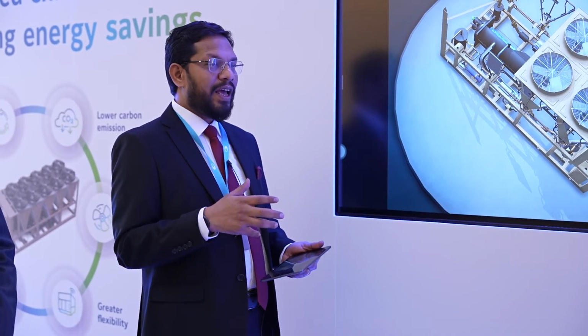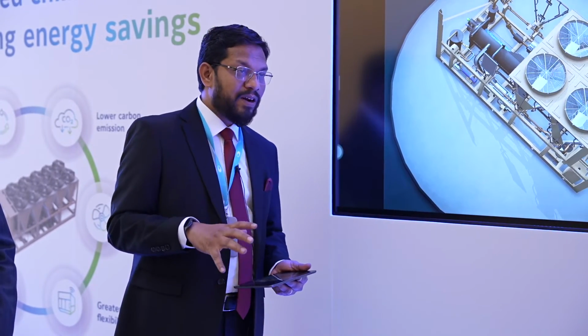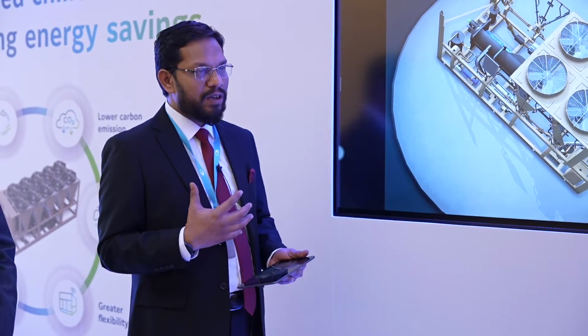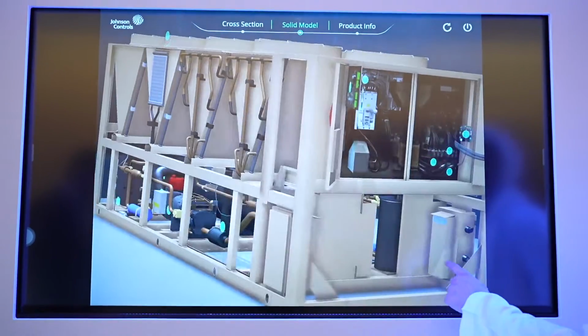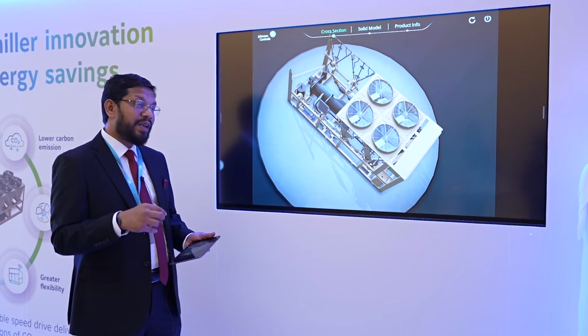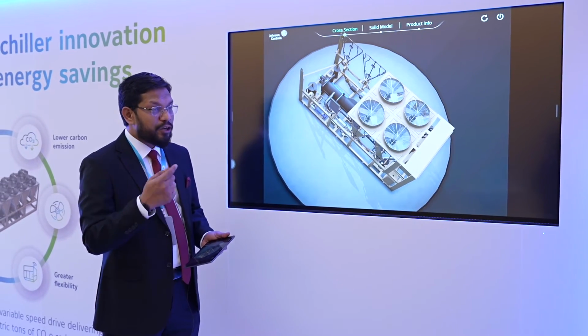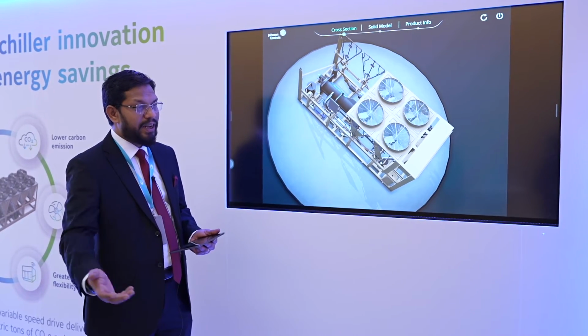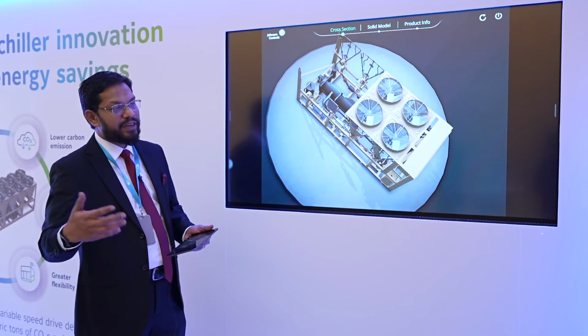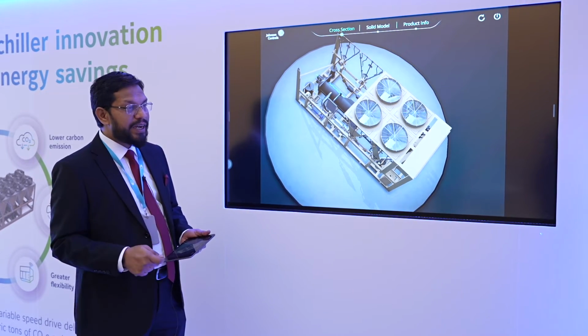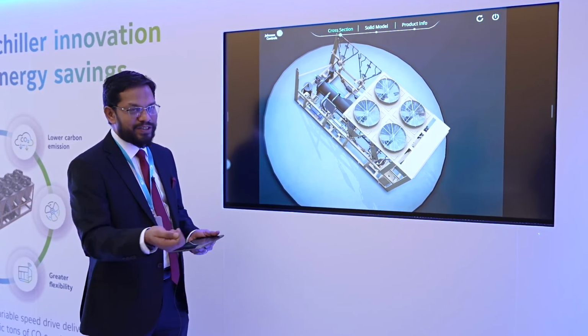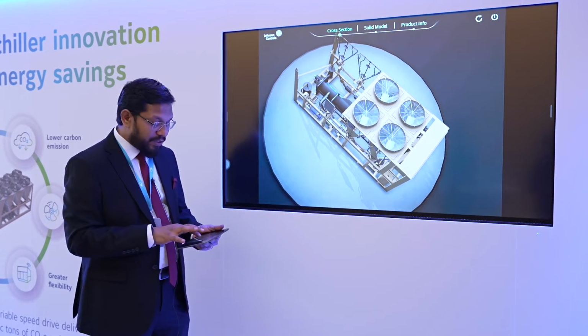We introduced a hybrid falling film technology, which has been patented by York for the past 10 years, where we put the water inside the tubes. So anytime there is scaling during the life of your chillers, after 10 or 15 years, there is the ability to clean those tubes with brushes. That is the next advancement we have made.